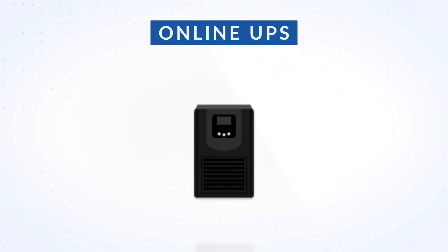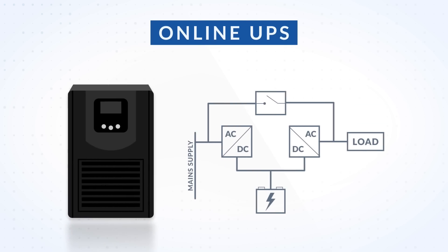The Online UPS always provides power to the load via double conversion. During proper operation, the power from the mains is converted from AC to DC. The DC voltage charges the battery and is converted back to AC through the inverter. This means that during a blackout, the power instantaneously goes to the load with almost no transfer time.